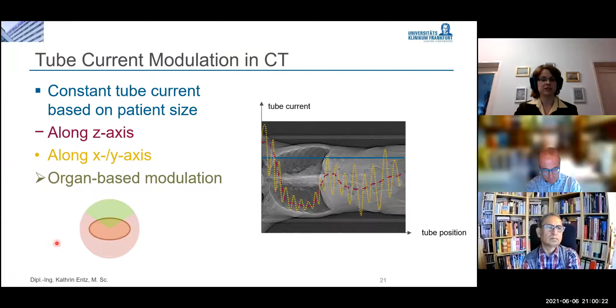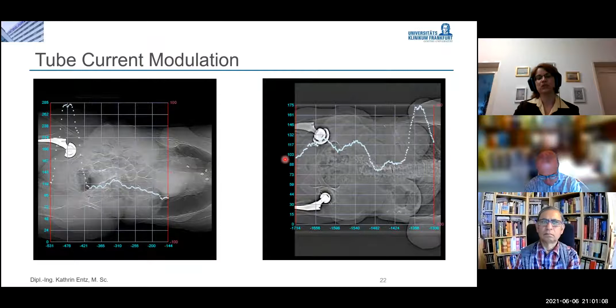Different vendors use tube current modulation in a different way. You have here two patients with hip implants, and you can see here on the left side that the CT scanner recognizes that there is an object there that is absorbing a lot of dose. So it is increasing the dose to a very high level and then decreasing it again. On the other hand, here on the right-hand side, this scanner also recognizes that there are metal implants, but it is not increasing the dose. Instead, it is using some metal artifact reduction so that it doesn't have to expose the patient to high dose values.